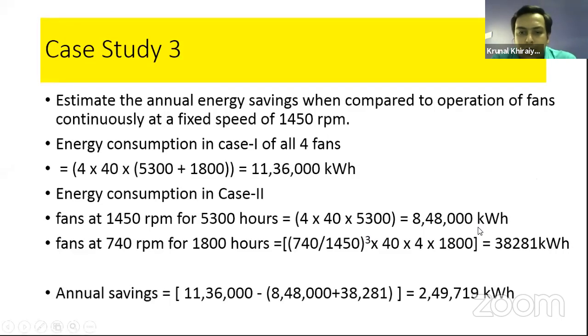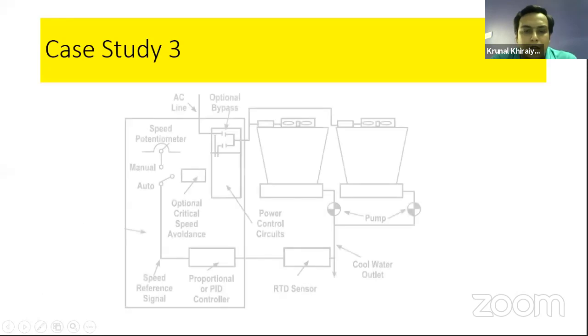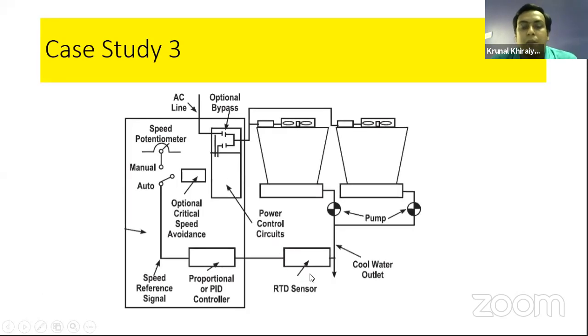consumption of power, that is the summation of both the two, 8,48,000. So finally, we achieved the savings of 2 lakhs amount, near about 2,50,000 kWh. Okay. So here I'm showing the schematics. We are using RTD sensors, which come out of the cooling water pump. And according to the PID controllers, our fan is operated at different speeds. So this is a schematic diagram.